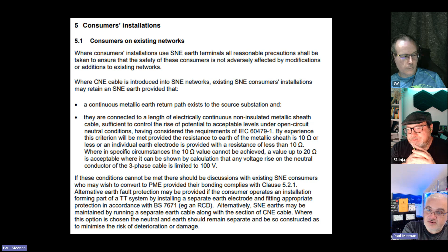So again, the customer pays for fitting appropriate protection in accordance with BS 7671, i.e. an RCD. Alternatively, SNE earths may be maintained by running a separate earth cable along with a section of CNE cable. Where this option is chosen, the neutral and earth should remain separate, constructed to minimise the risk of deterioration or damage. We'll look at a photo in a minute to show that. Some people see these earth wires going along, sometimes to an electrode, but it's about maintaining a separate earth. The earthing terminal, section 521.